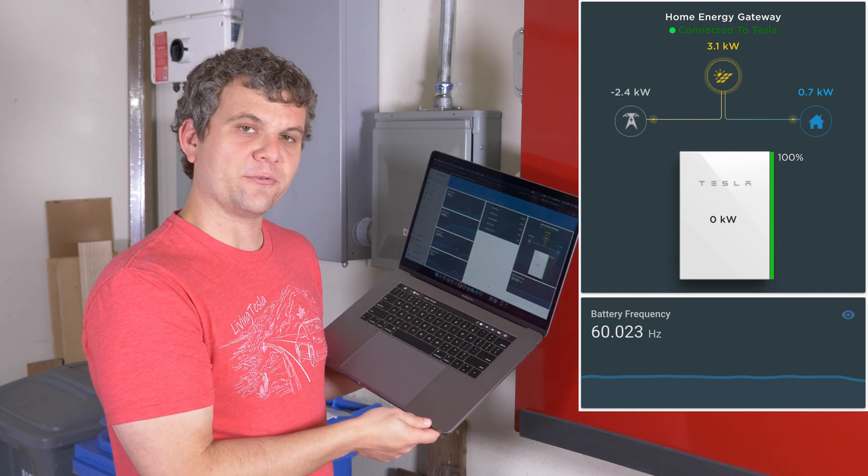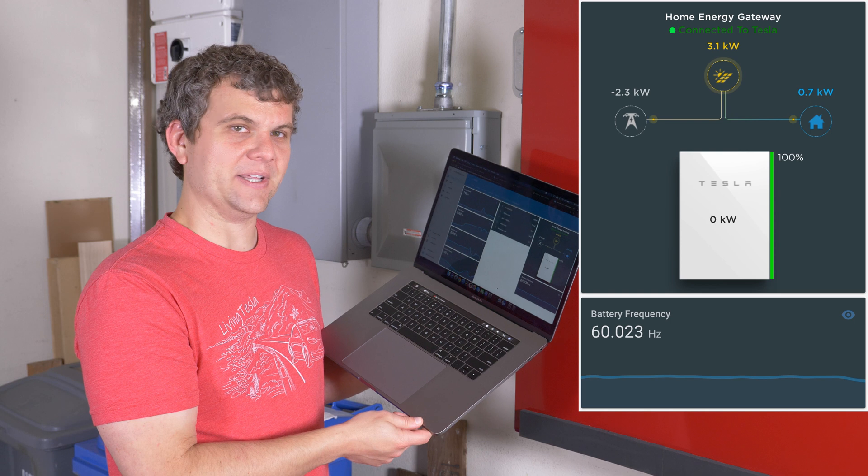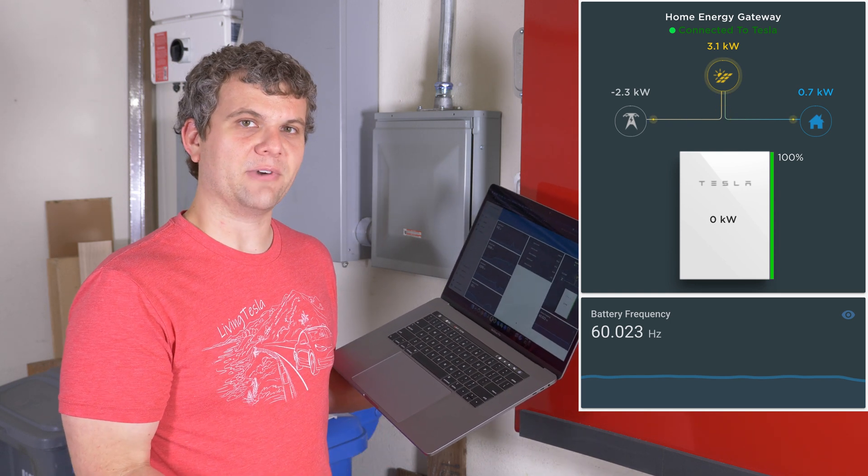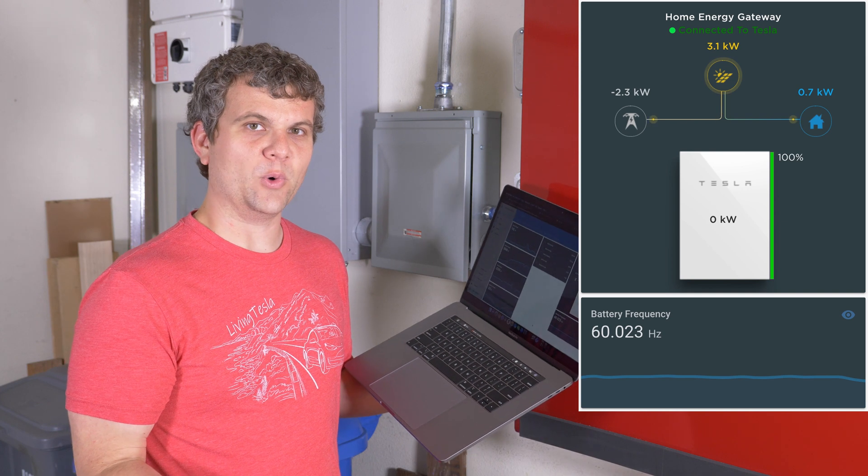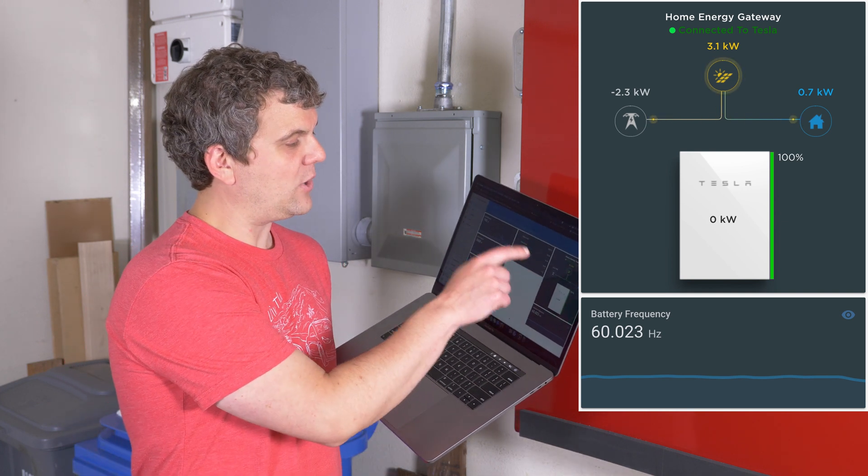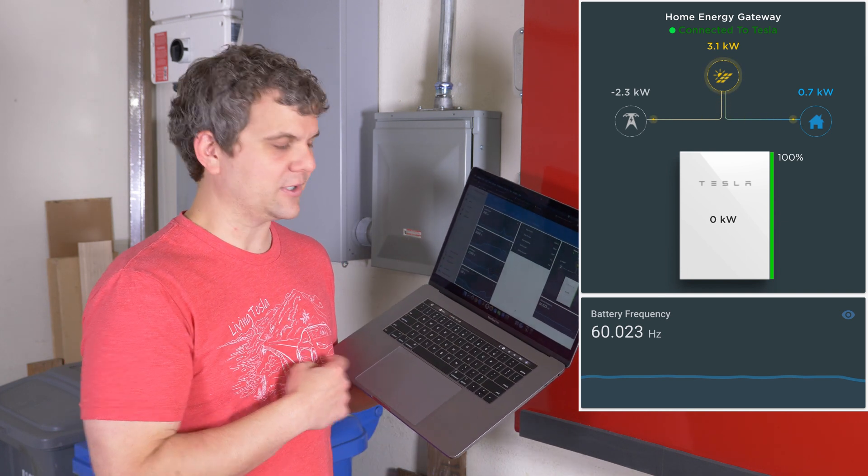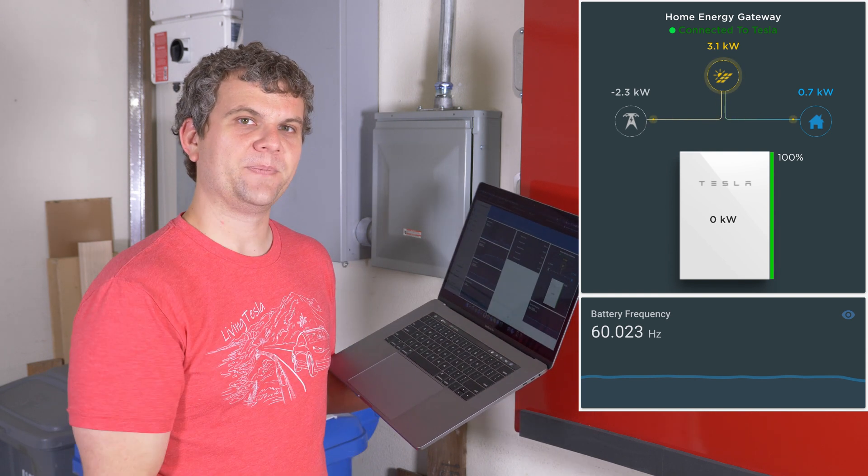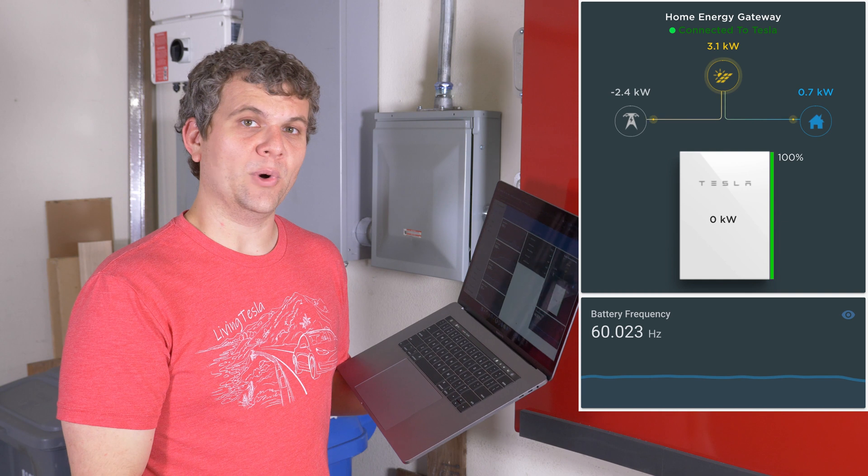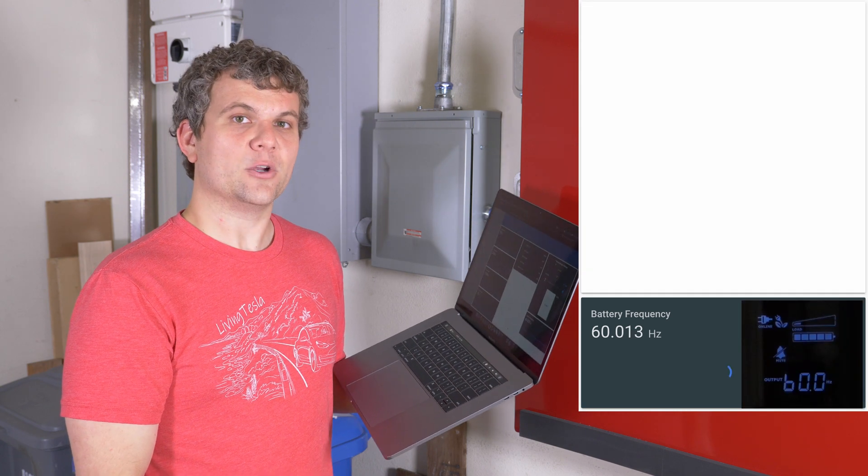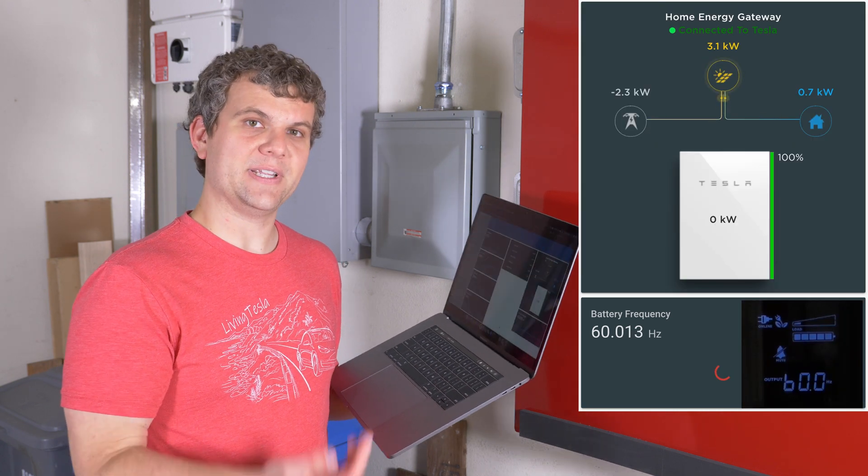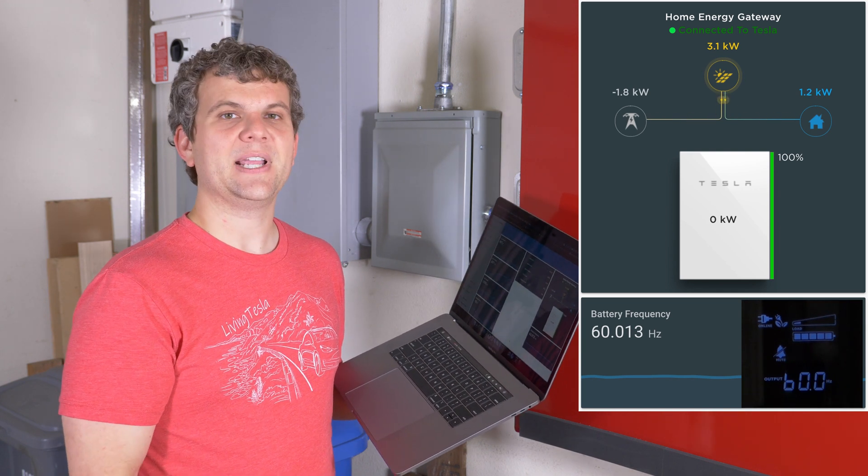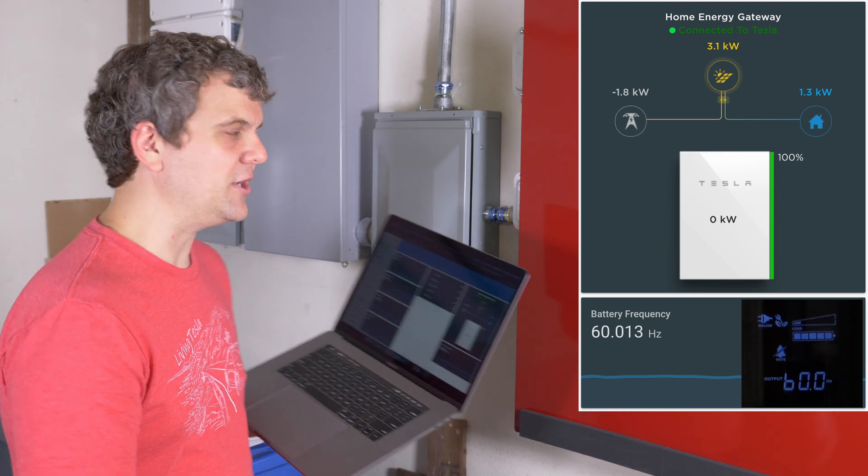We're sending 2.3 kilowatts back out to the grid. So this is a situation where if we lost the grid right now, power has nowhere to go. The Powerwall is going to shut down the solar. So we're expecting this battery frequency to go up. Now, I also have the camera pointed at the UPS so we can see what it's doing. It should stay online and we should see its frequency only go to 62 instead of 65. So let's do it.